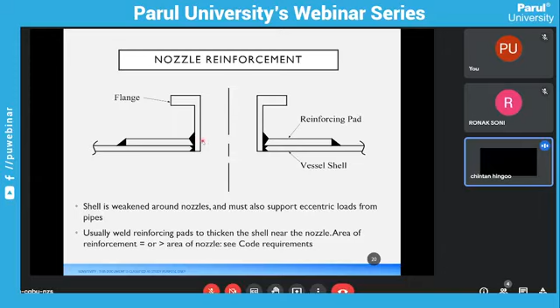So here you can see that one reinforcing pad is provided on the external side of the vessel shell, which basically has the function to strengthen the pressure vessel at this junction. Whenever you are making a cutout, this area will be lost. So equivalent area needs to be provided either by a reinforcing pad or by making the nozzle neck wider or thicker. All those reinforcing pad calculations and vessel wall openings are given in the boiler pressure vessel code.